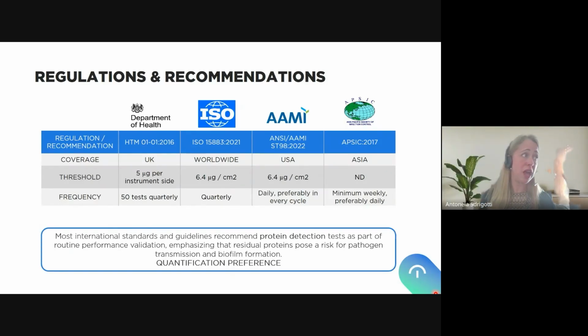Not mandatory, but it is a recommendation, because what I intend to show here, just with the same SOPs that I have shown at the beginning for validation and monitoring, for verification, there is also a trend in suggesting protein testing to verify that actually my washing process is removing organic residues from the instruments, and not only setting up or monitoring the parameters, but monitoring the outcome, which is protein-free instruments.